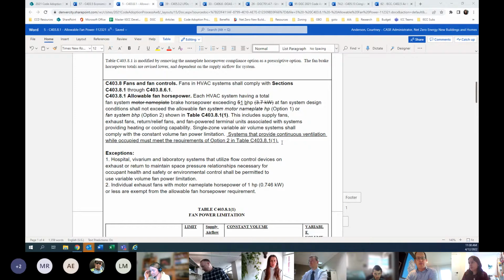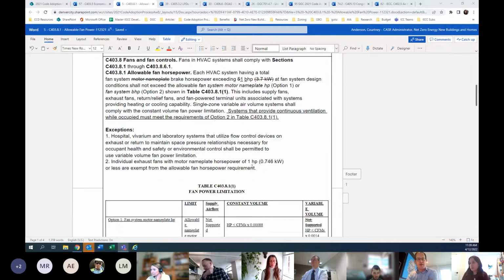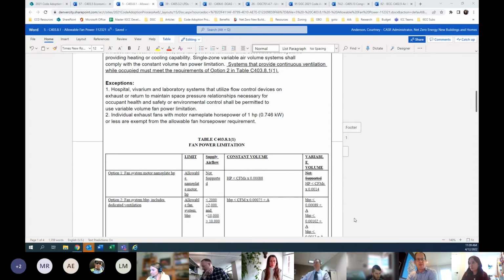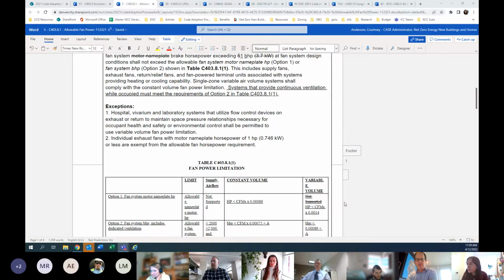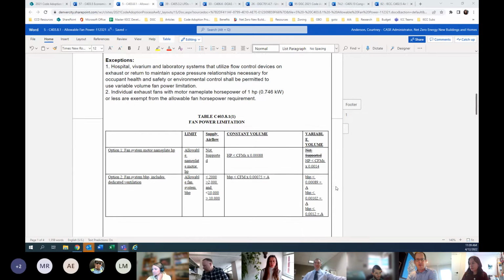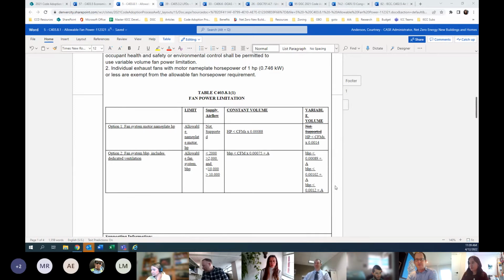Systems, there's a clarifying note mainly to cover the DOAS type systems. Systems that provide continuous ventilation while occupied must meet the requirements of option 2. The exceptions haven't changed here, so hospitals and laboratory systems, process type systems are not covered under this. And then individual exhaust fans with nameplate horsepower 1 or less are exempt from the requirement. So this again is based on a study that was done through other jurisdictions. So the structure of the proposed change matches the current IECC code for Denver, but the main difference is that the limits for both constant volume and variable air volume fan systems have been reduced somewhat.